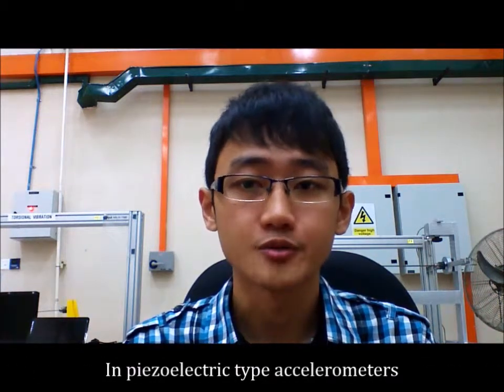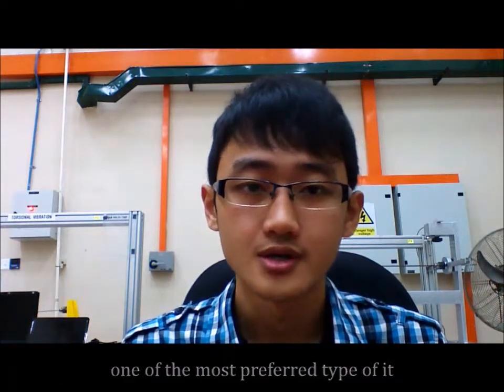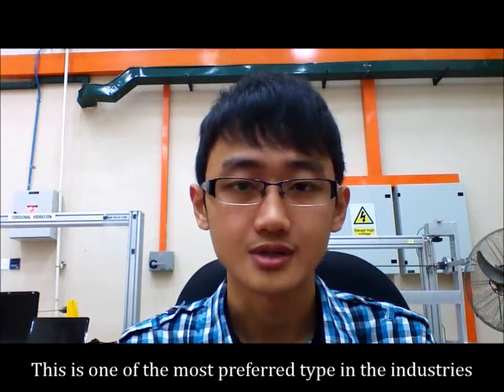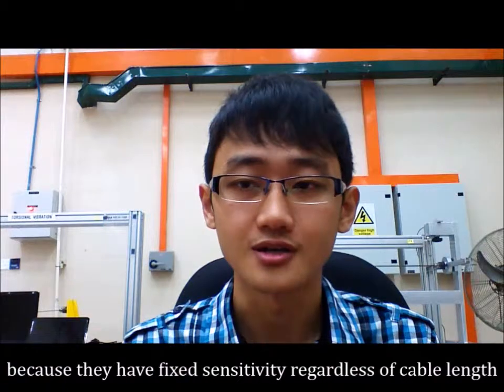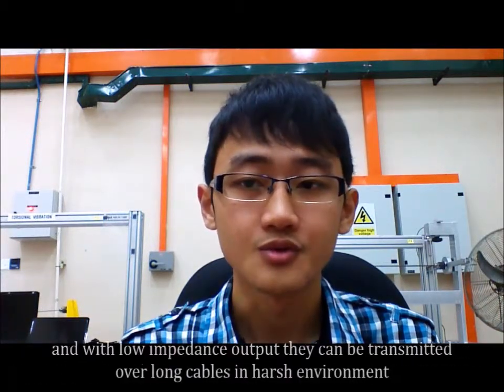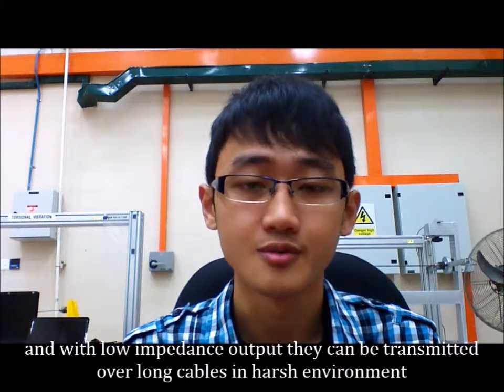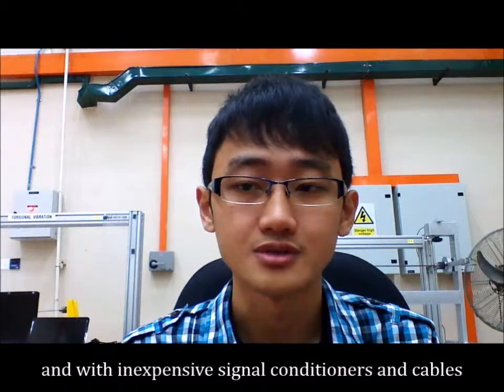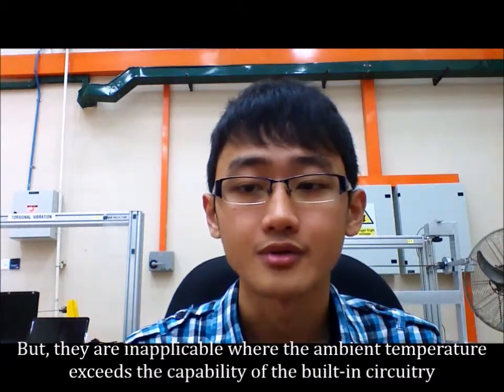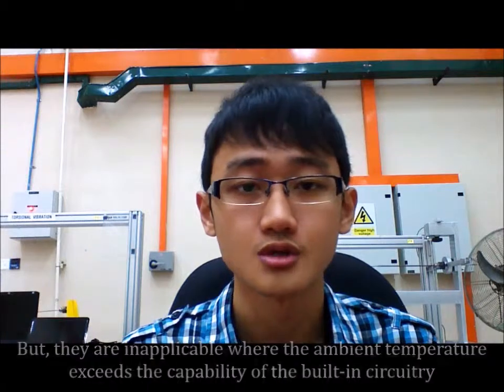Among piezoelectric type accelerometers, the voltage output type, one of the most preferred is the IEPE piezoelectric sensor. IEPE stands for Integrated Electronic Piezoelectric. This is the most preferred type in the industry because they have a fixed sensitivity regardless of cable length and quality. With low impedance output, they can be transmitted over long cables in harsh environments with inexpensive signal conditioners and cables, and have broad bandwidth. But they are inapplicable where the ambient temperature exceeds the capability of the built-in circuitry, which is usually less than 125 degrees Celsius.